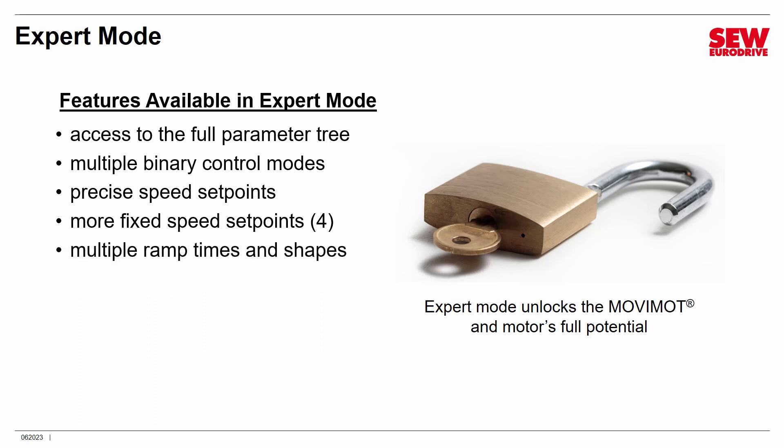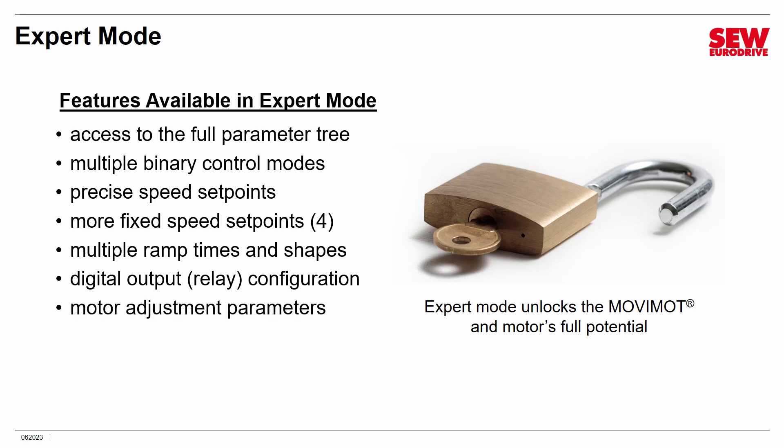You also get more control over your ramps. In Easy Mode, you basically have just a single ramp value set with the T1 dial, giving you the same up and down ramp times. In Expert Mode, you can have independent up and down ramps, and you can also alter the ramp's shape. You have more control over the single digital output — the relay contact. In Easy Mode, the relay contact simply indicates whether the Movimot is ready or not, but you can assign the relay to other status signals.